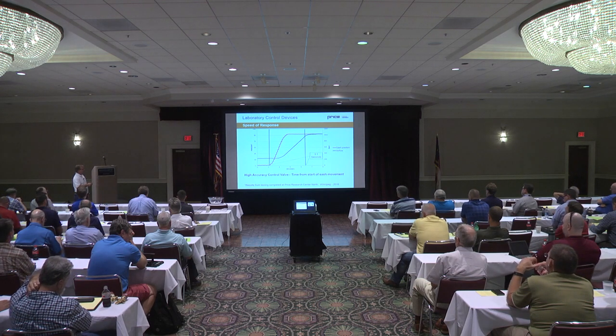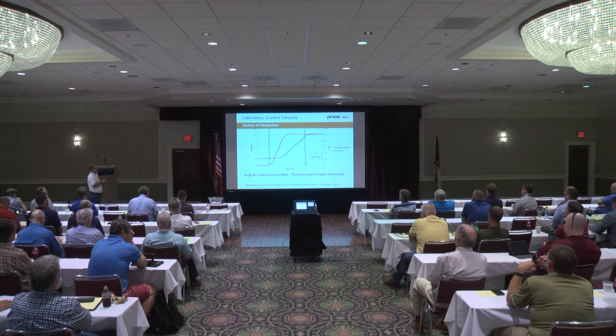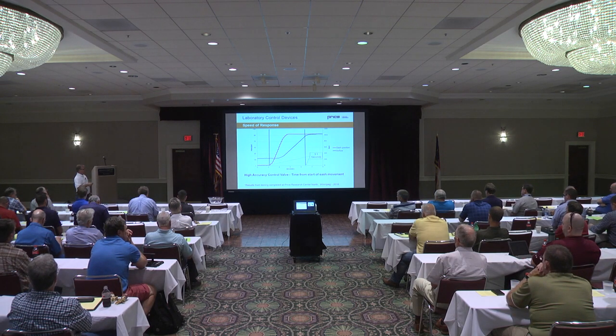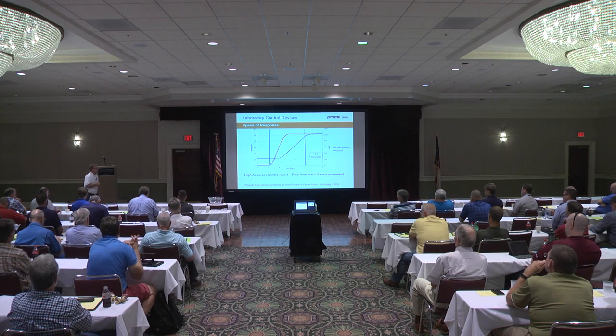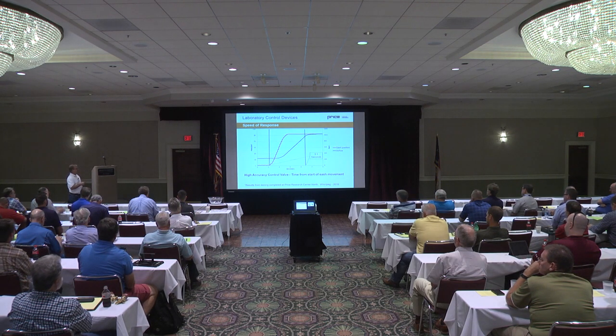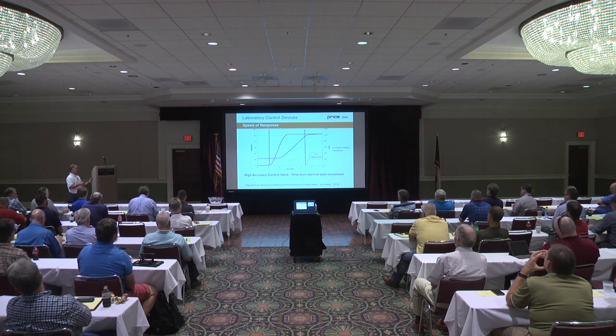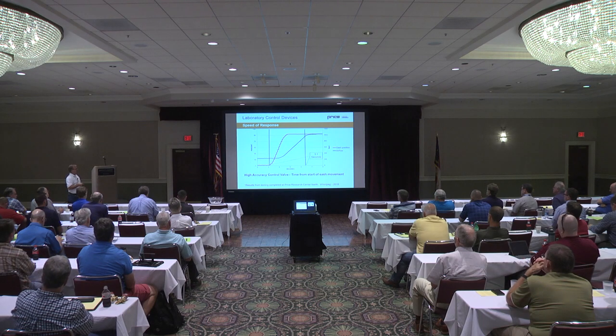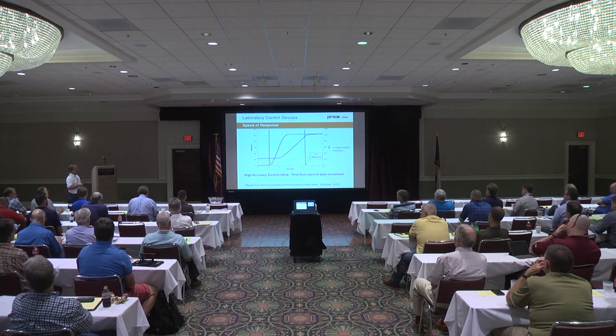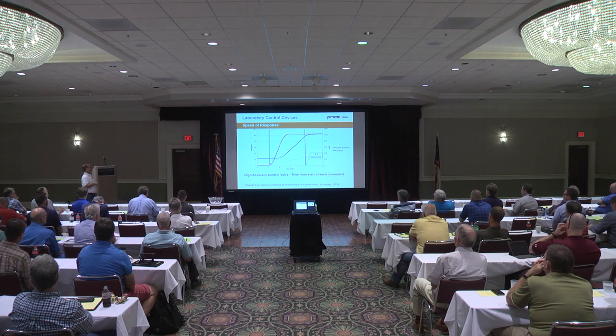On the speed of response, from the time the sash starts moving to the time the sash stops moving and the flow is stable, is 3.1 seconds. Again, fairly acceptable when it's less than 3 seconds. I guess you could split hairs on that. Somebody might have issue with that, but still very good response time on those type of devices. Cross-flow sensing device in this application, I don't even have a chart for it, but it's way outside these time frames.